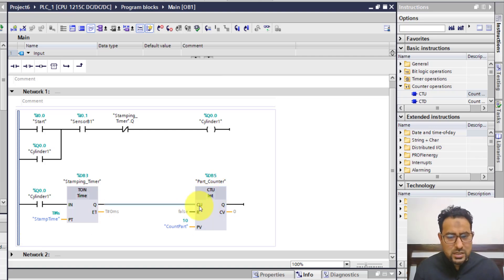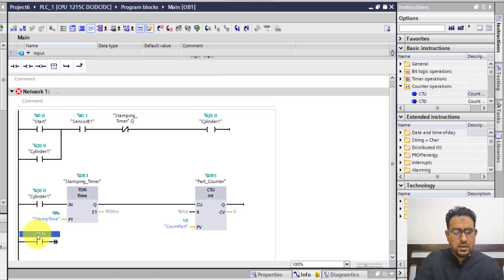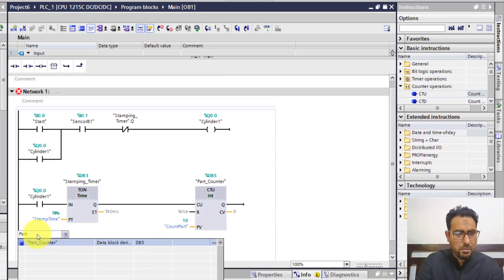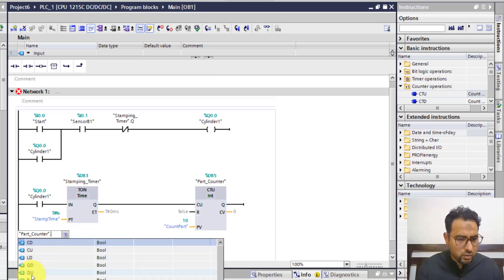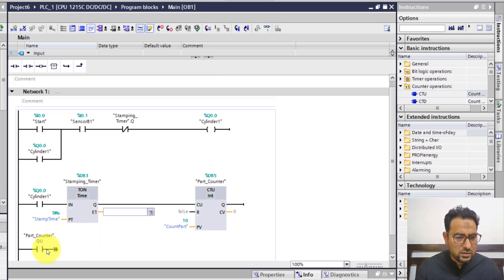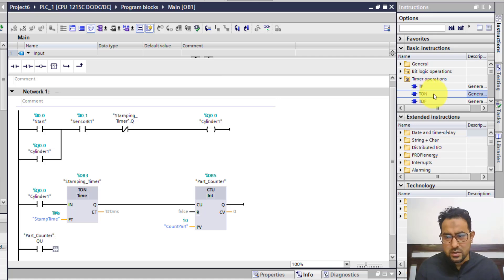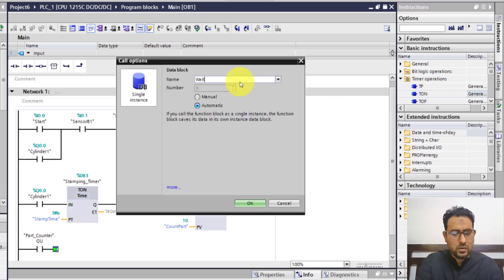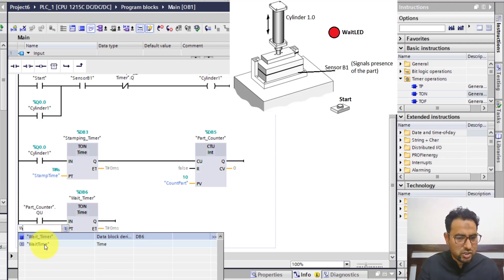After this, when the counter has counted to 10, we want a wait timer to run. On a new rung, I'm going to use the counter done bit — the counter Q-bit. The name of my counter is part counter, and inside it I have the Q-bit. When this counter is done counting, it goes high. After that I need a timer, so I'm going to use a new timer — I'll name it wait timer. The preset value will be the wait time constant I defined.